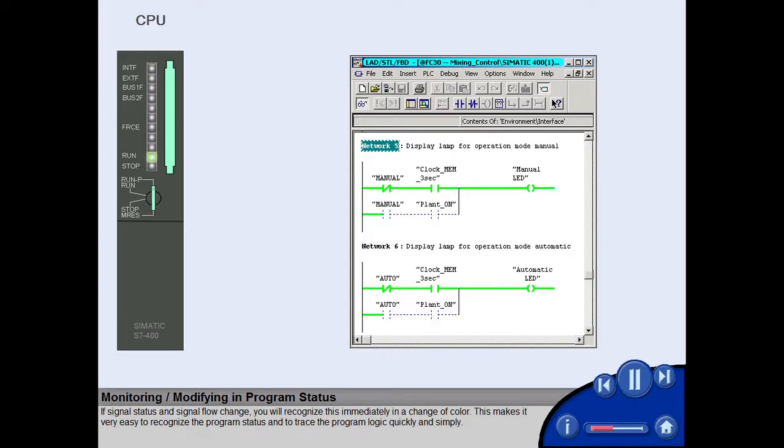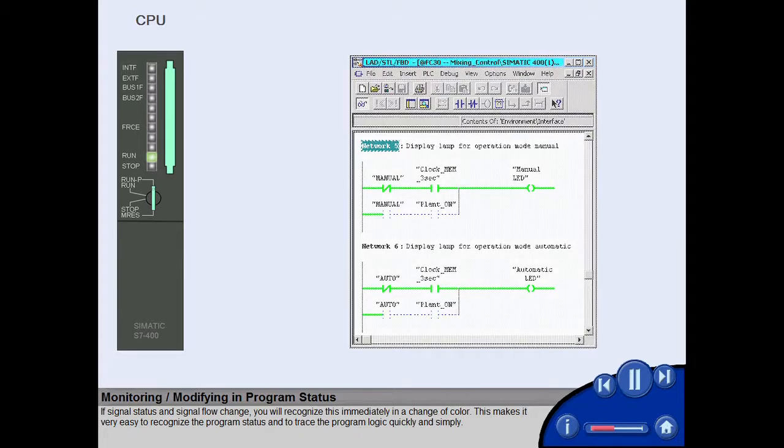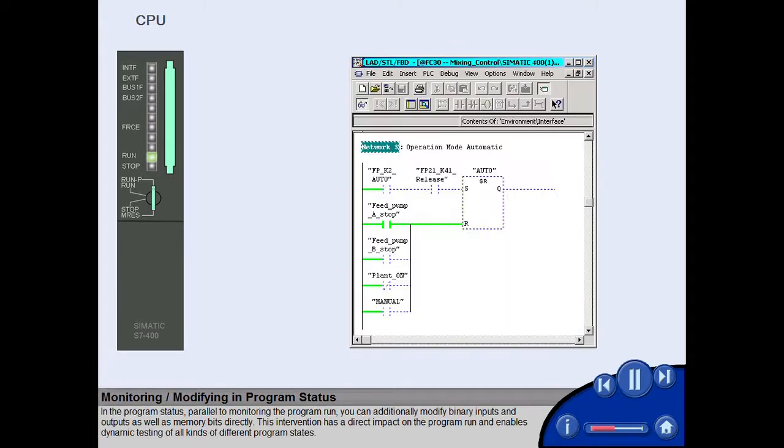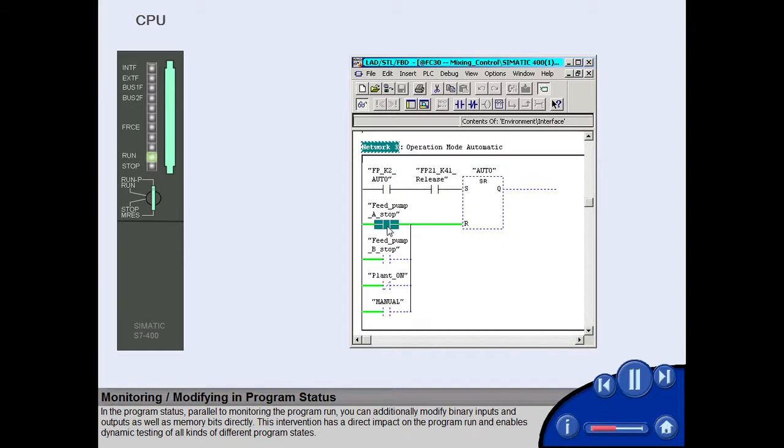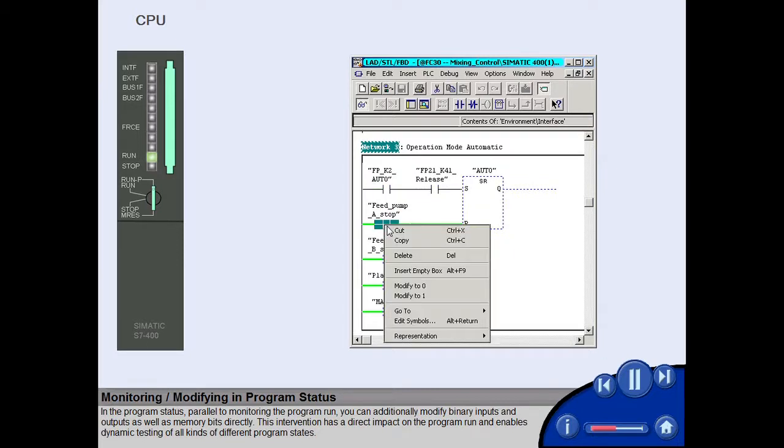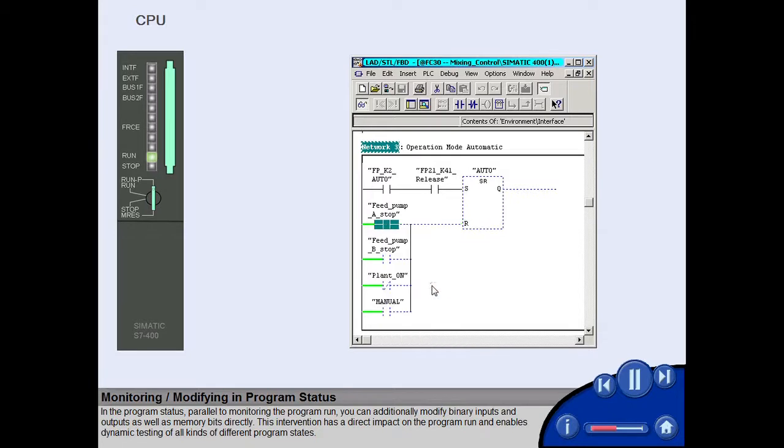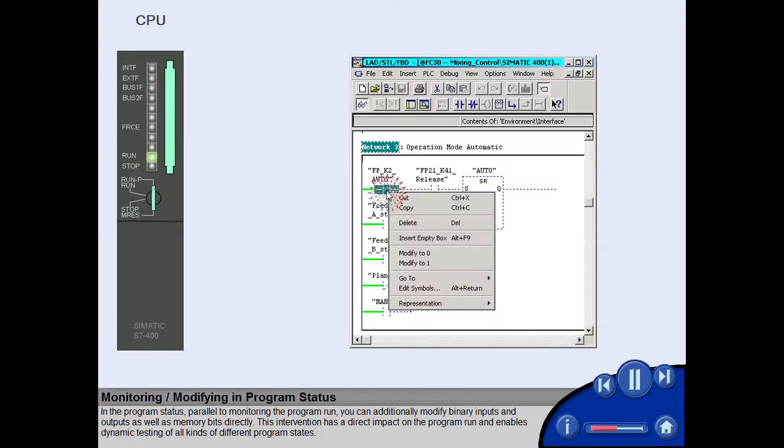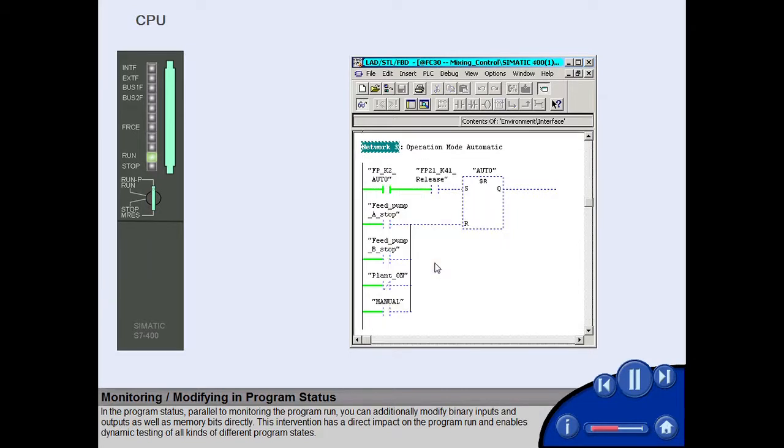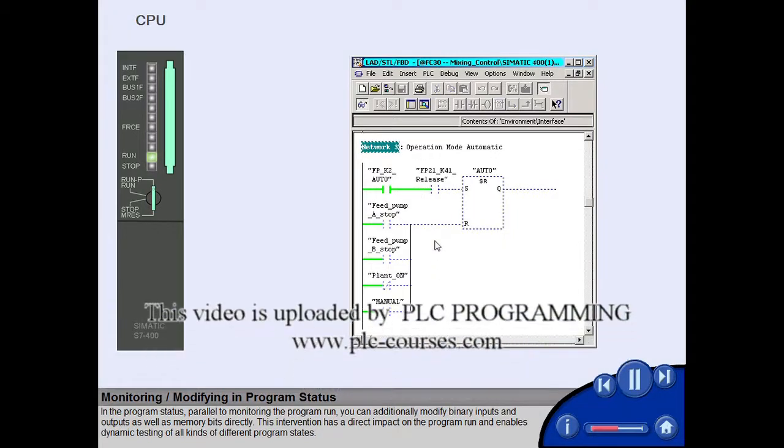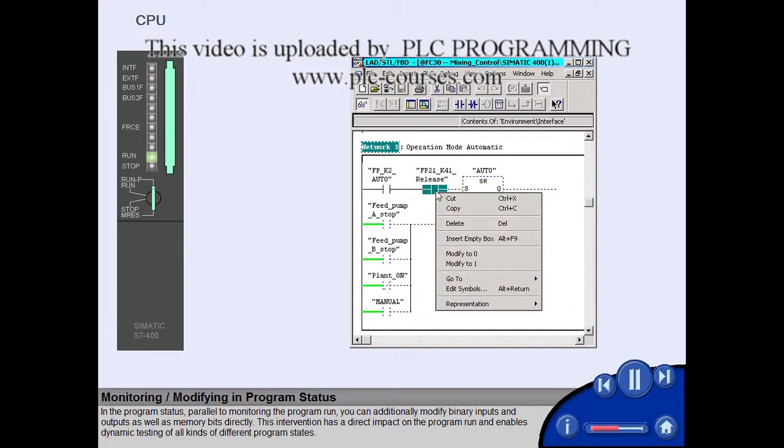This makes it very easy to recognize the program status and to trace the program logic quickly and simply. In the program status, parallel to monitoring the program run, you can additionally modify binary inputs and outputs as well as memory bits directly. This intervention has a direct impact on the program run and enables dynamic testing of all kinds of different program states.